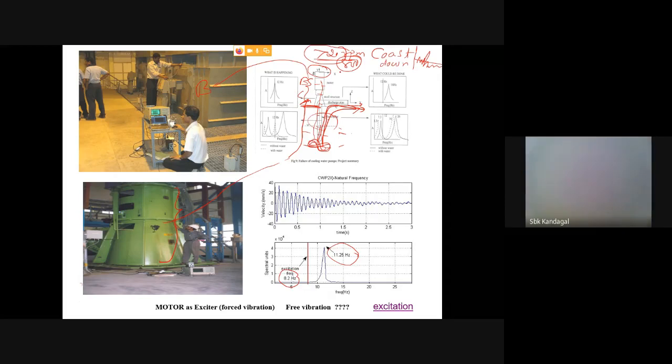So this is one of the practical ways of finding out the system properties in rotary systems. It is called a coast down study. You take it to high speed and switch it off. Any subsystem that is undergoing resonance will show up, and from that particular RPM you can correlate which RPM is critical, and then find out how to mitigate and overcome it. One cannot do forced vibration using an electrodynamic shaker for rotary systems. The only thing done in industry is the coast down study. The existing motor or generator itself can excite this rotary system by varying the speed and then switching it off.